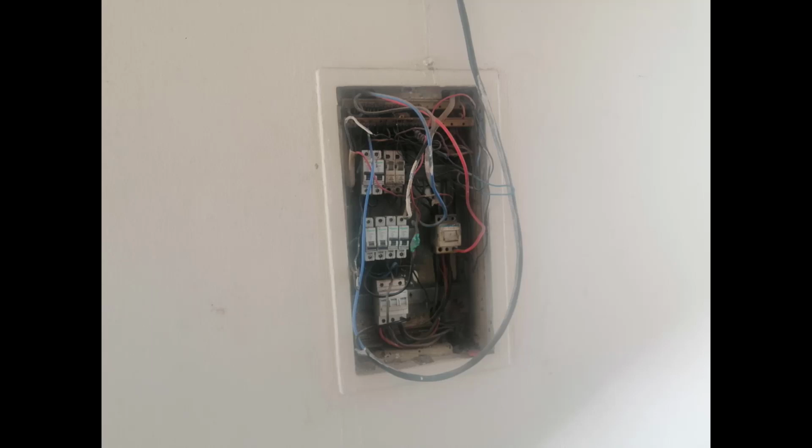During those periods when we were isolating units in the facility and identifying faulty areas, we discovered that there is a distribution board in one building that is connected to all those other buildings where we identified the AC units were faulty. At some point, we felt there were several things that mattered in this case. It's possible that either the connection from that small building to the other buildings is the fault, or the other AC unit compressors are the fault.